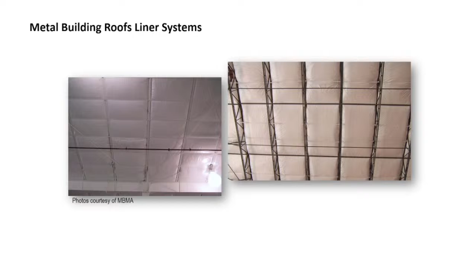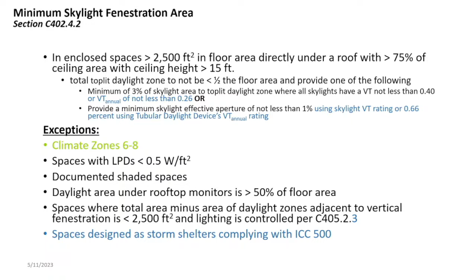Minimum skylight areas. Again, stop me if you want to talk about something. If you have a building greater than 2,500 square feet, at least 15 feet high, you need at least 3% skylight area to the top lit daylight zone. And we have a VT for those. We got so much to cover. I'm going to keep moving unless you got something you want to talk about.